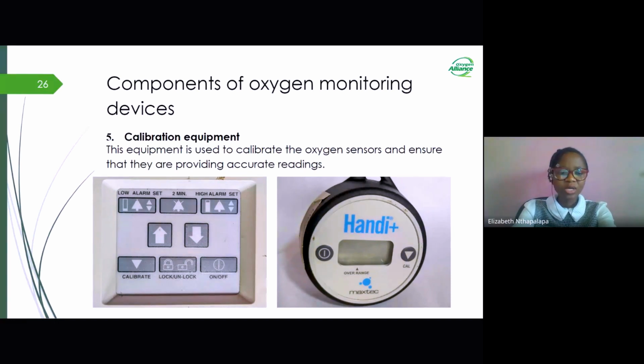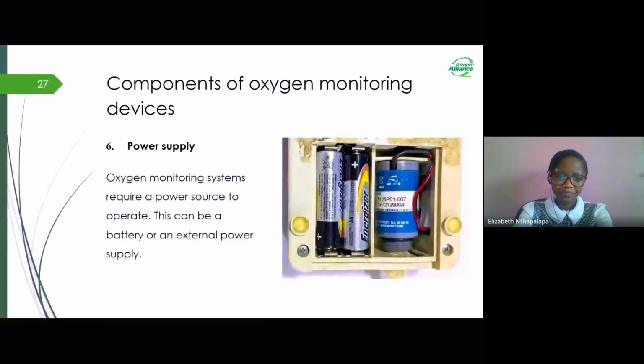Next, let's look at the power supply. For each and every oxygen monitoring device to run, it requires a power source. It can be an external power supply, or we can use a battery, as we can see in our picture here that we have an electrochemical analyzer with batteries in it. So this analyzer uses batteries for it to operate well.